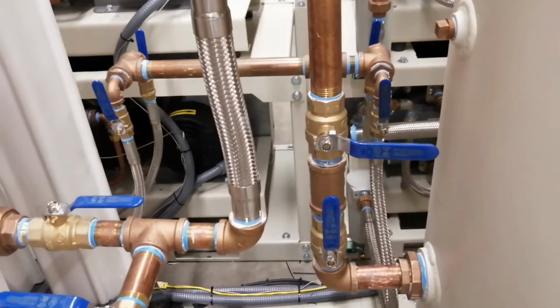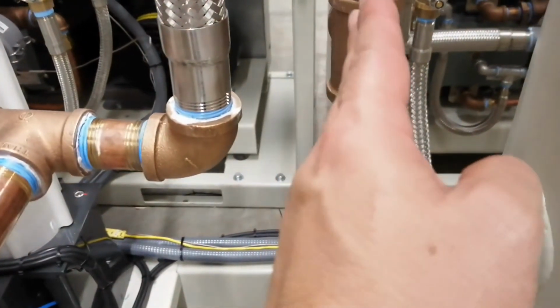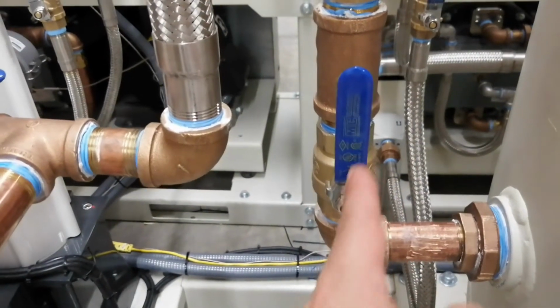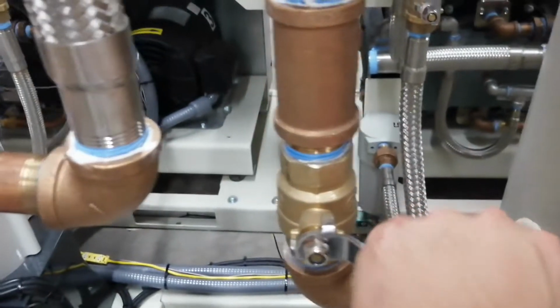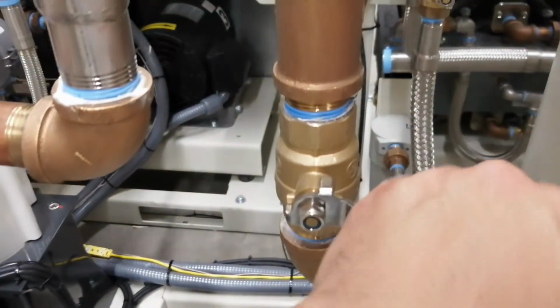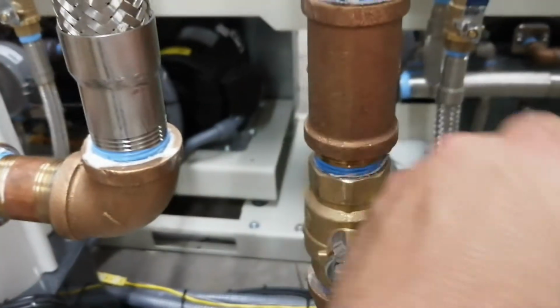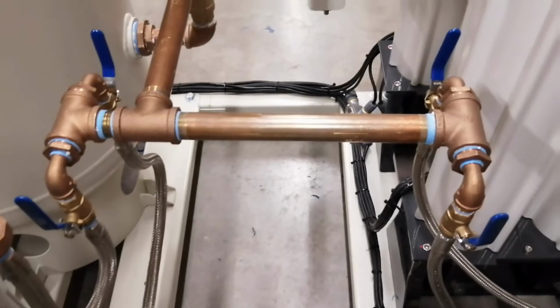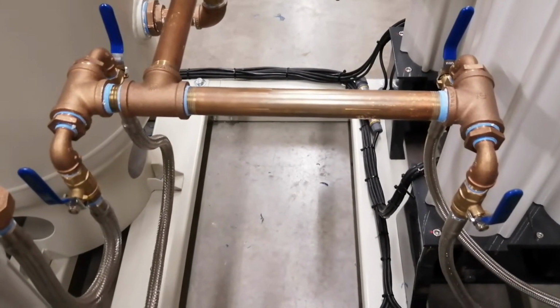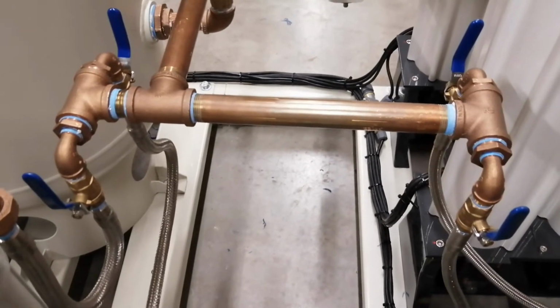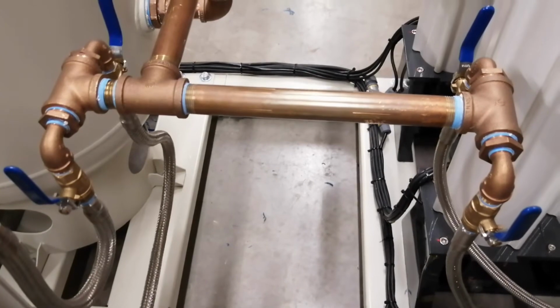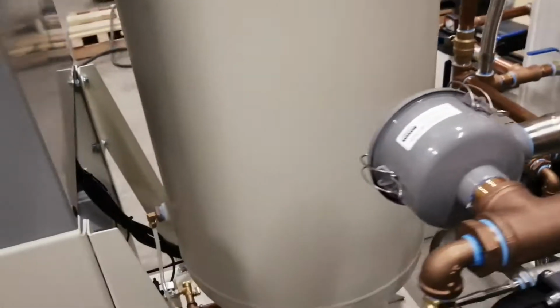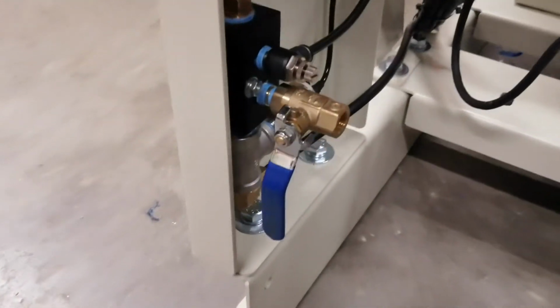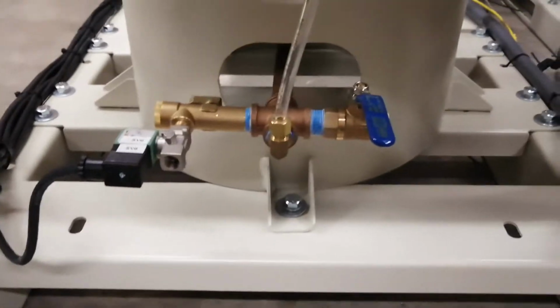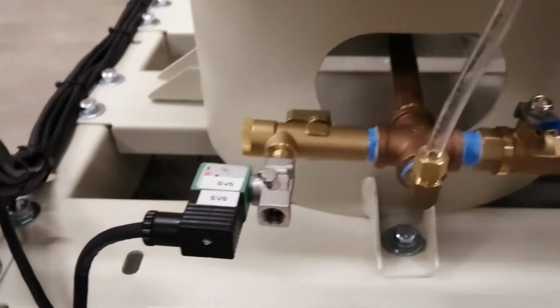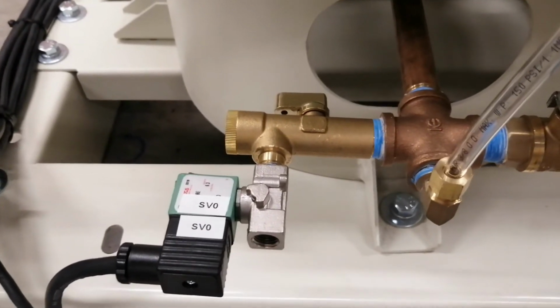Remember, a valve is open when the handle is in the parallel position regarding the pipe, and closed when it's perpendicular to the pipe. Open, close. In normal operation, every discharge ball valve, manual ball valve for each pump must be open in the manifold. Sample valve must be closed. Manual drain valve must be closed, and the automatic valve, the strainer filter, must be open.